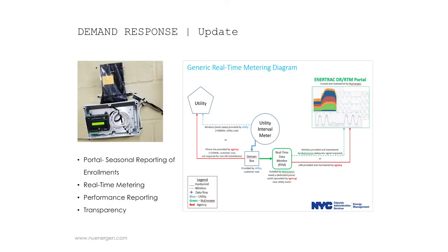And that can be done very easily. Here you have the utility meter, an hourly interval meter. Most utility companies require a demarcation box wired to the utility meter because they don't want third parties like my company wiring into it directly. No one touches that, but you can take a pulse output from the demarcation box by putting a real-time meter on the building.